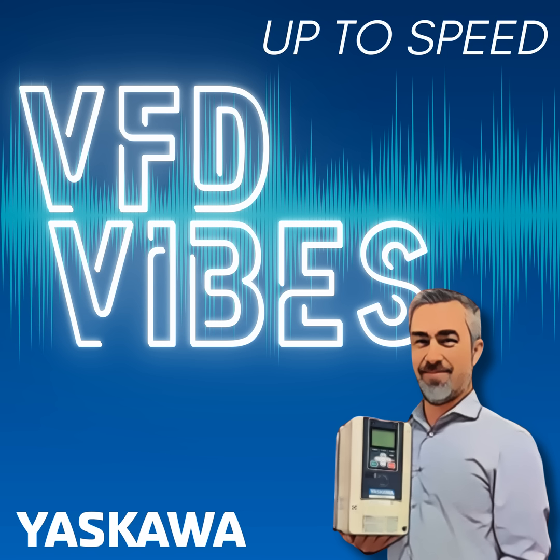An active harmonic filter, however, behaves completely differently. This is a device with semiconductors with switching built in, and what it does is it's connected to the line and it listens for harmonic currents and it injects opposing harmonic currents. There's a perfect analogy to how an active harmonic filter works: your noise-canceling headphones. How do noise-canceling headphones work? Well, just like I described. You have your headphones on, unwanted noises are coming at you from all sides, and the headphones are listening and producing opposing sounds that effectively cancel out the unwanted noise and create silence.